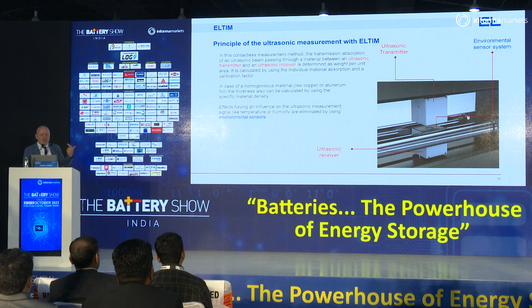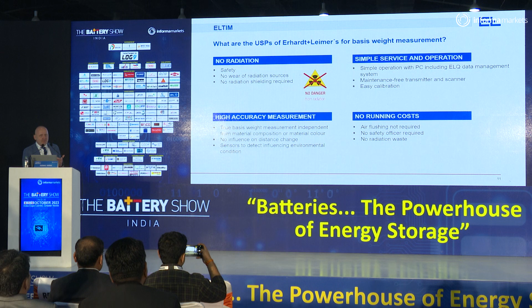The unique selling points of Erhardt and Leimer's basis weight measurement: the most important, there's no radiation. This means no wear of radiation sources and no shielding required. The high accuracy of the measurement. As mentioned earlier, it's a true basis weight measurement of the material, with no influence from distance changes. Sensors are able to detect environmental conditions. Simple service and operation, because this is one of our key targets. And no running costs, which means no safety officer required, as is the case with beta ray, and no radiation waste. These are the main items of the unit, which you can also see at our booth.